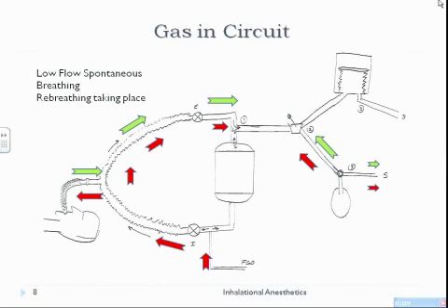but also part of it will allow the person to rebreathe. If you really put it at very, very low flow states, almost 100% of the gas comes back. So that person stays asleep with agents that they already breathed off. That really saves you money, because you can give less anesthetic since you're rebreathing the gas that came out.